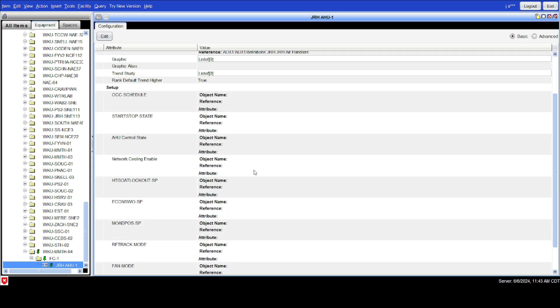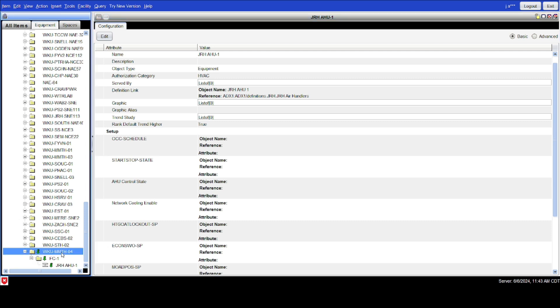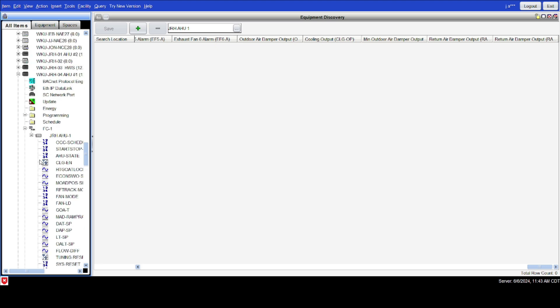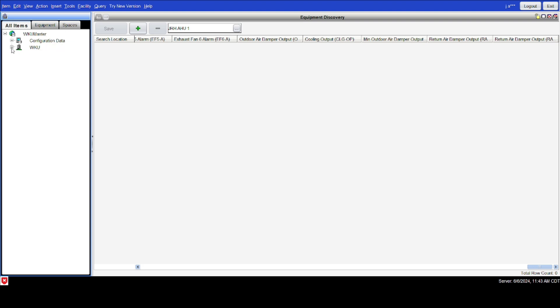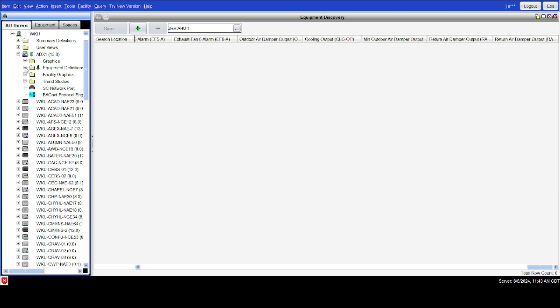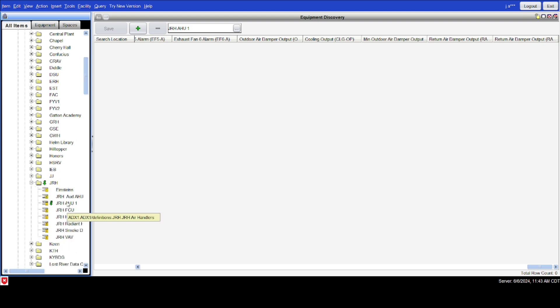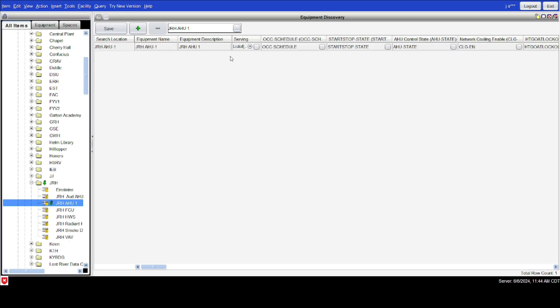If you tried to use that equipment object that it creates, it's going to display weird in your system — you're not going to get what you expect. By doing this it modifies the equipment definition and the equipment object to the way that we need it. The equipment object — if you go back and check out those other videos — is what we add to spaces within Metasys. This is where you would link the serving relationships and set up the other features within Metasys. You don't want to just go adding points from the network tree into your graphics; you can, but it's bad practice.